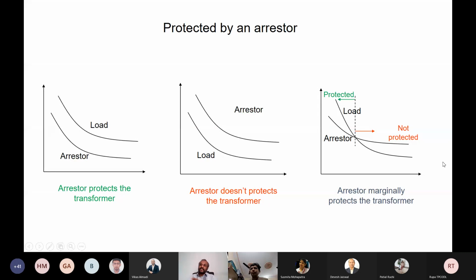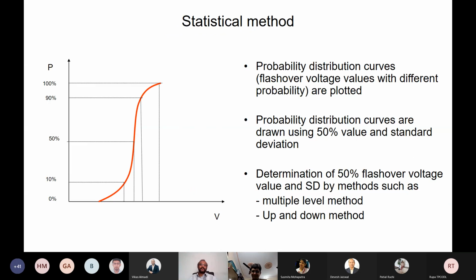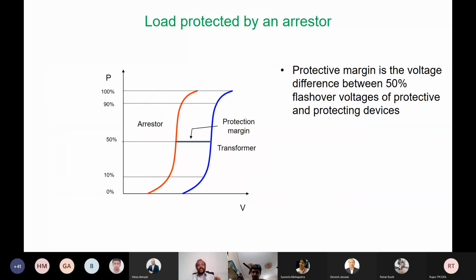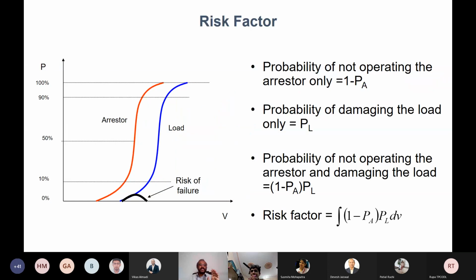But if it is like that, the third curve, then up to some extent, the arrestor will protect the load, and after that, the load will protect the arrestor, which is not your intention. And it can also be shown by a statistical method as well. If you plot the curve probability of breakdown versus voltage, then there should be a fair margin between the characteristics of the arrestor and the characteristics of the transformer. So if it is only having a separation like this, your load or the transformer will be protected.